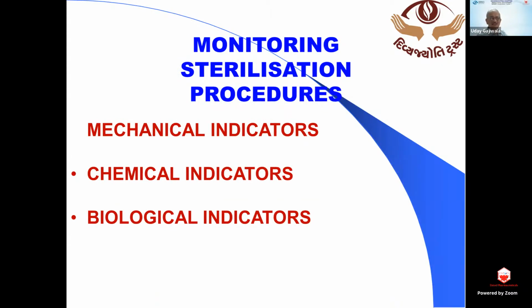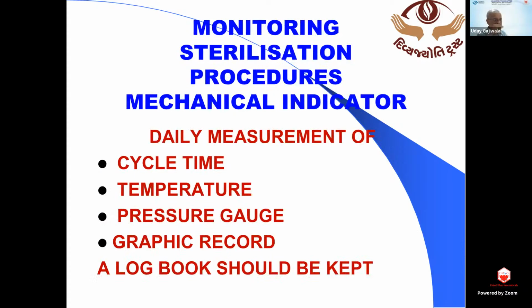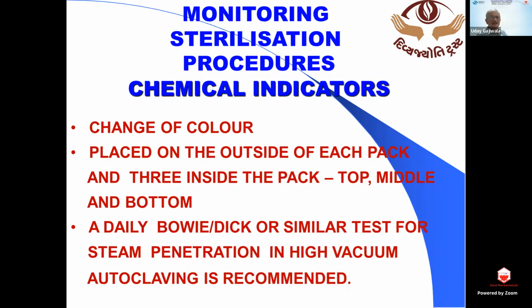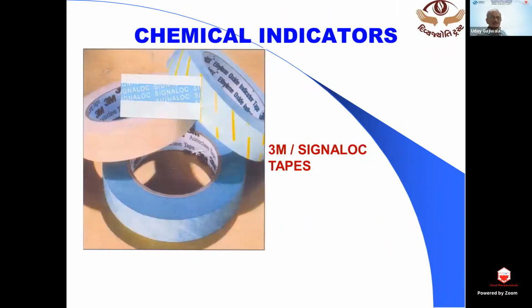So as far as monitoring the sterilization procedure is concerned, we can monitor by mechanical indication, we can use chemical indicator, we can use biological. As I told you, autoclave cycle logbook needs to be maintained. Then chemical indicator, Dr. Purvasha alluded to 6 different classes of indicators. Chemical indicator is class 1. It works by change of color, but this change of color depends only on one parameter, temperature. So if the color of the indicator tape, the chemical indicator is black, jet black, that means that the temperature was attained. It does not indicate sterilization.